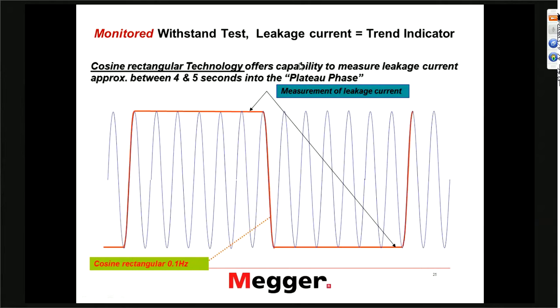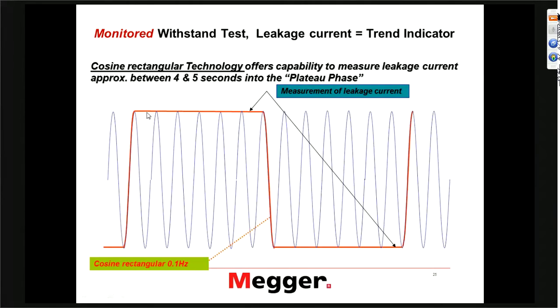One of the withstand test technologies — the cosine rectangular — looks basically like a 60 Hz transition with a plateau phase of five seconds, then another 60 Hz transition. We can measure leakage current at the end of the plateau phase, in contrast to when we have a sinusoidal VLF test where we cannot measure leakage current.